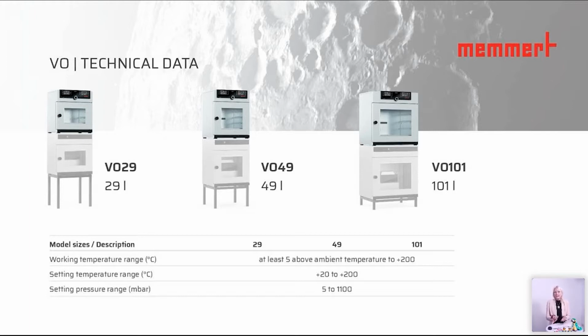And of course, when we talk about evaporation, what does it mean? We need a pump to take out this fume from the interior, so that takes out the air. So that means here we have a pump housing and a pump and a subframe. If you consider this full segment, which means we have a vacuum oven with pump and housing and the subframe, then we have a correct size for the operation. So it's very nice to operate at this height. Then further, let's look at the temperature and pressure ranges. So temperature is from 5 above ambient to 200 degrees. And we have a setting temperature of 20 to 200 degrees. And you can set a pressure from 5 millibar to 1100 millibar.